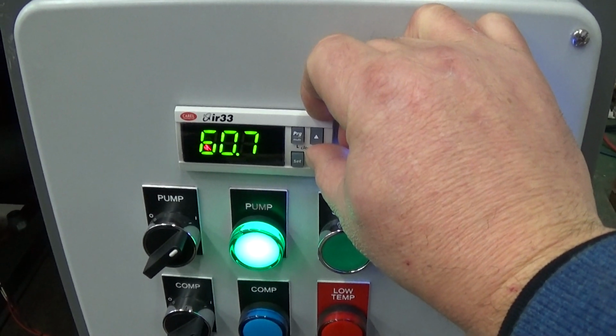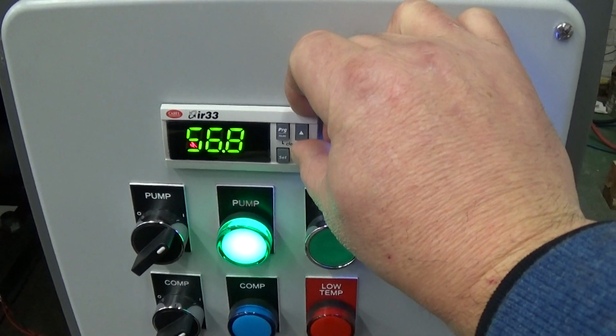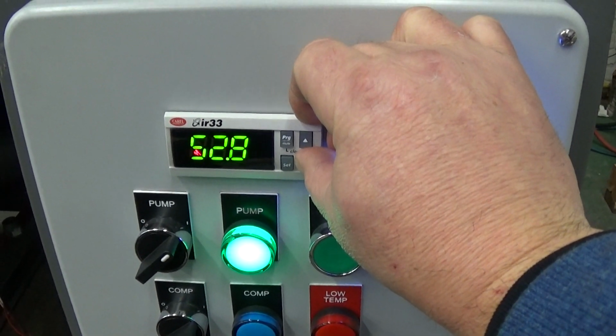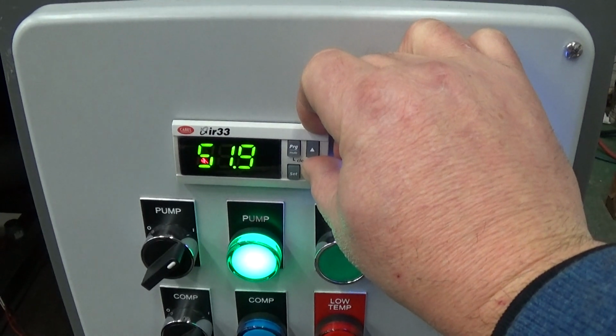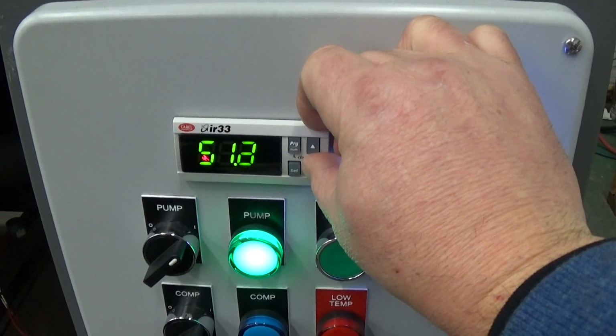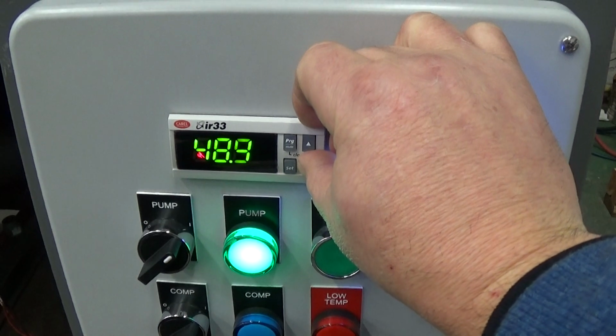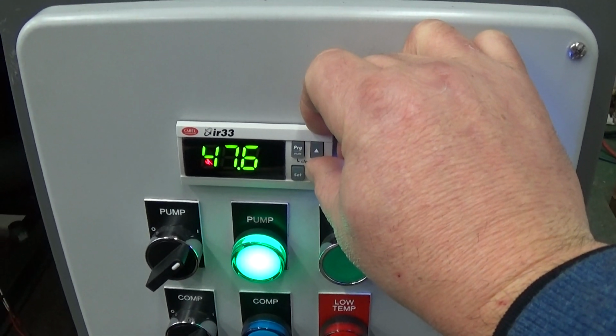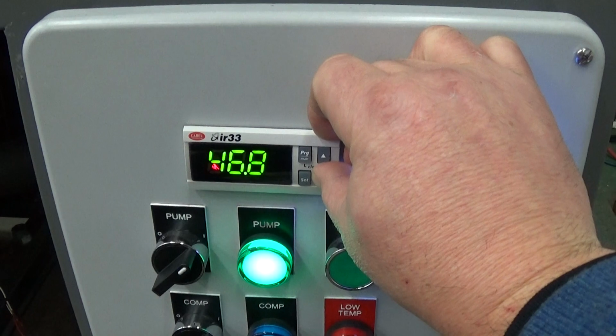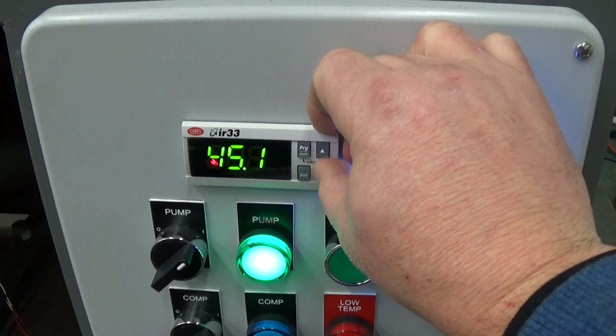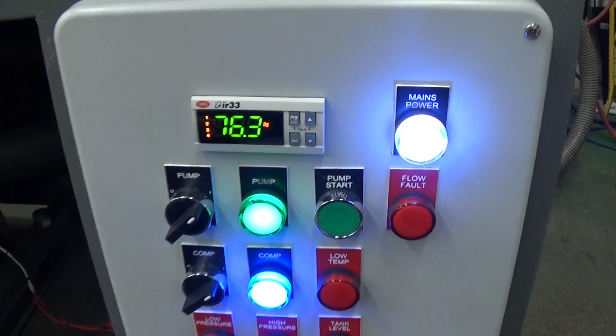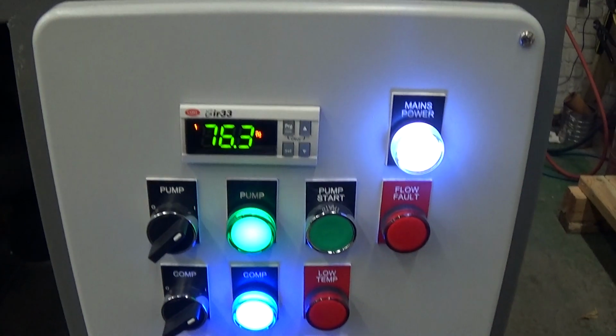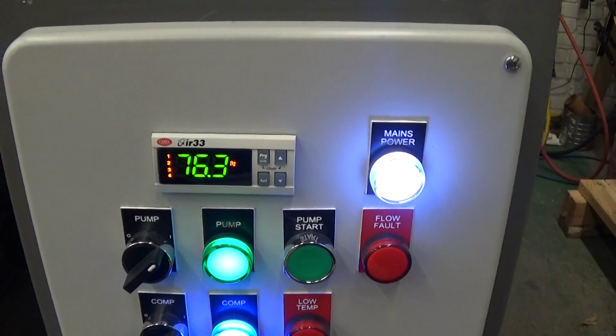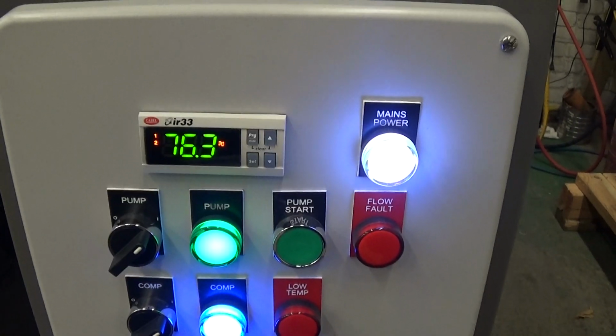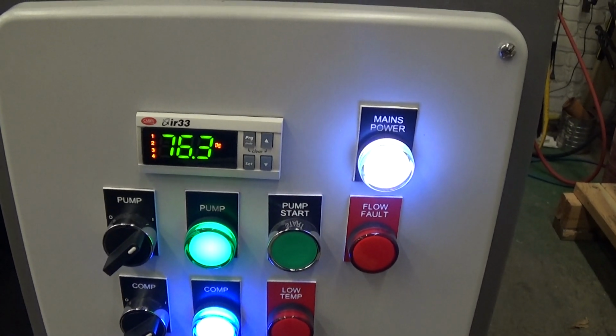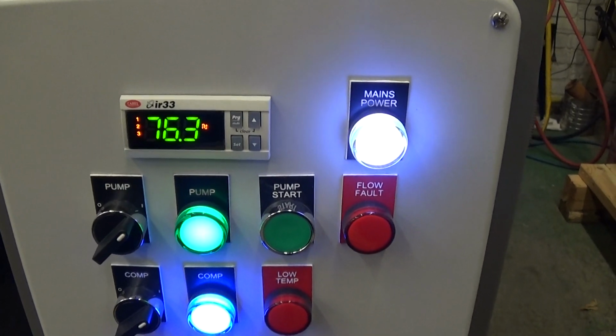This same unit is approved to go to 25 Fahrenheit glycol temperatures. I just press set again, but it will default back to that 75 setting if I went one tenth more. So our scroll is just starting up and our fan is just starting to cool.